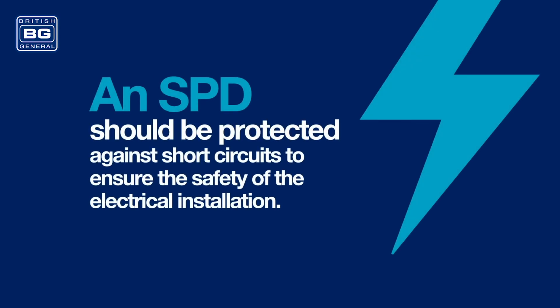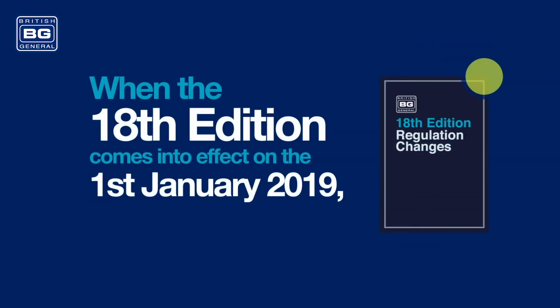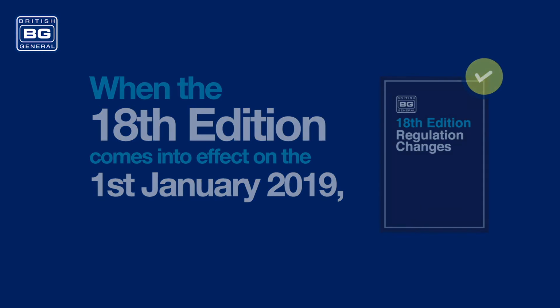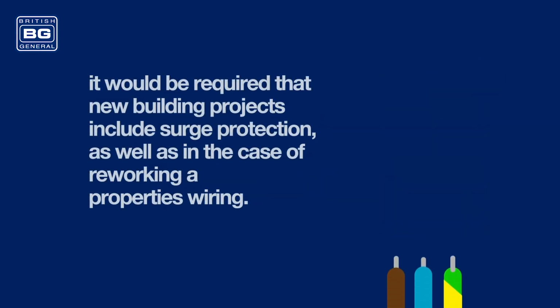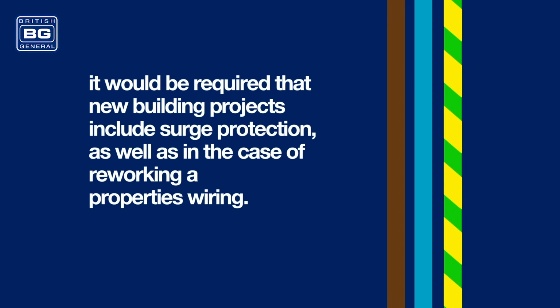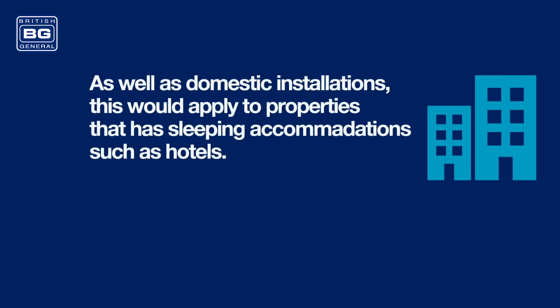An SPD should be protected against short circuits to ensure the safety of the electrical installation. When the 18th edition comes into effect on the 1st of January 2019, it will be required that new building projects include surge protection, as well as in the case of reworking a property's wiring. As well as domestic installations, this would apply to properties that have sleeping accommodations, such as hotels.